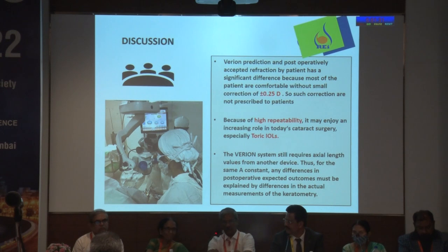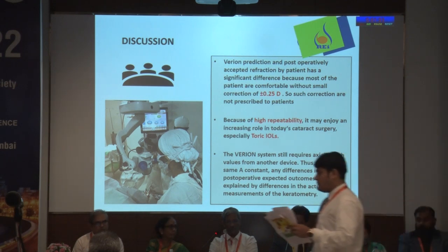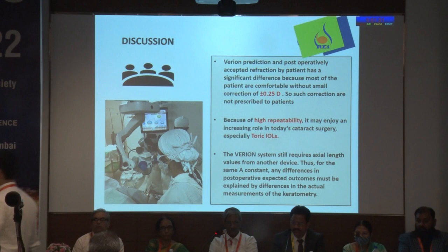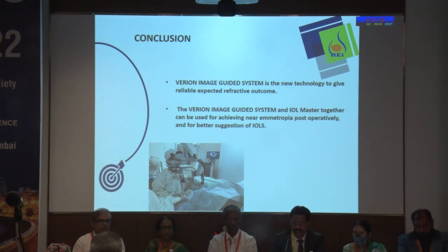The Verion system still requires axial length values from another device. Thus, for the same A constant, any difference in postoperative expected outcome must be explained by the difference in actual measurement of keratometric readings. To conclude, the Verion is a new technology to give a reliable expected refractive outcome. Verion and IOL Master together can be used for achieving near emmetropia postoperatively and for better IOL selection.